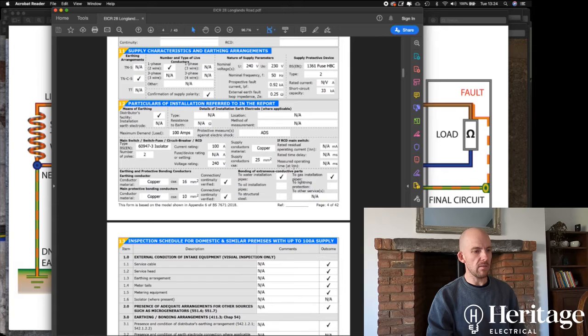Right, so then we've got the maximum demand of the installation. Now you can calculate this, and it might be more important to do that if you've got a commercial or industrial premises. But again, in the interest of time, when we're doing domestic stuff, generally take that value either from the size of the fuse or the maximum current rating of the main isolator that you've got in your consumer unit, which is usually 100 amps.